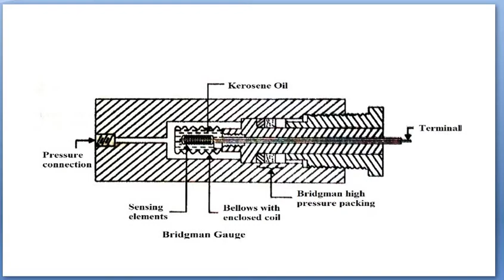The fine wire used in this type of gauge is Manganin or gold chrome. Manganese is preferred because it has a pressure coefficient of resistance of 25 into 10 power minus 12 Pascal per minus 1, and total resistance around 100 ohms. Although gold has a similar pressure coefficient of resistance, around 10 into 10 power minus 12, not much different, it is preferred in many applications since its resistance temperature coefficient is half that of Manganin.